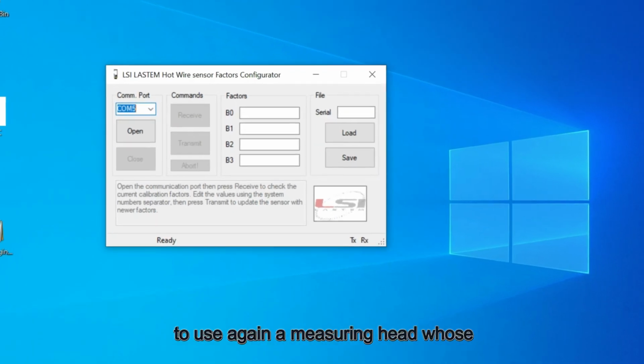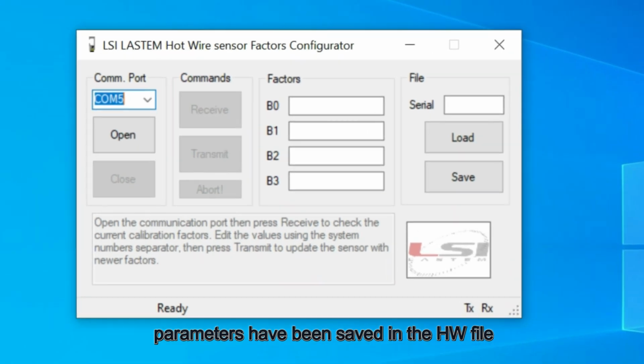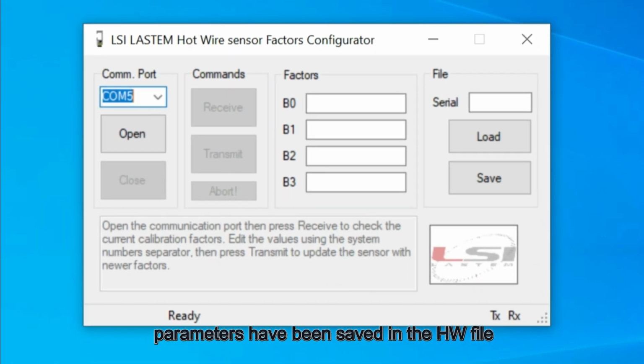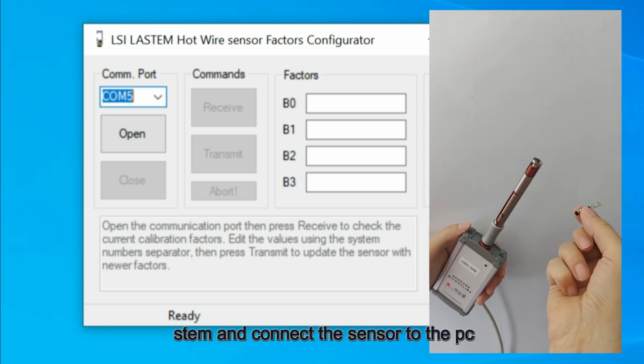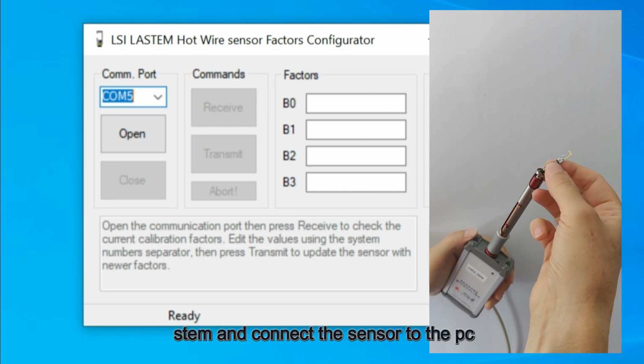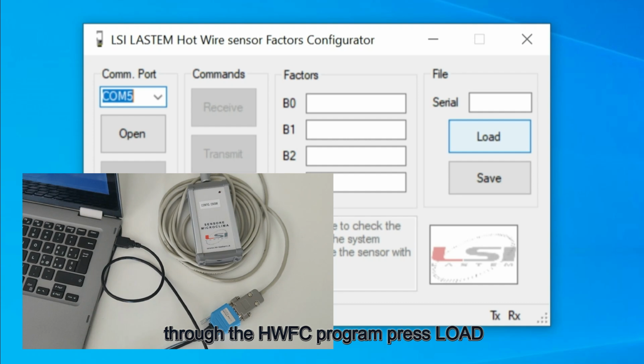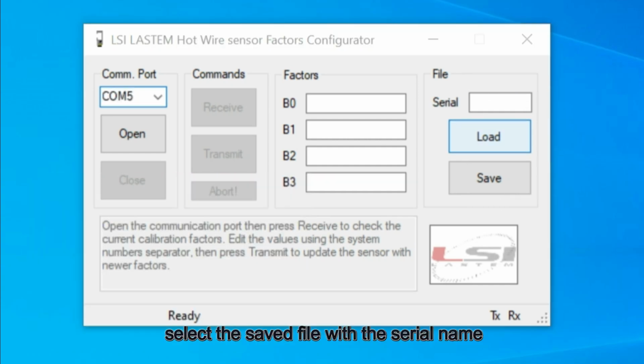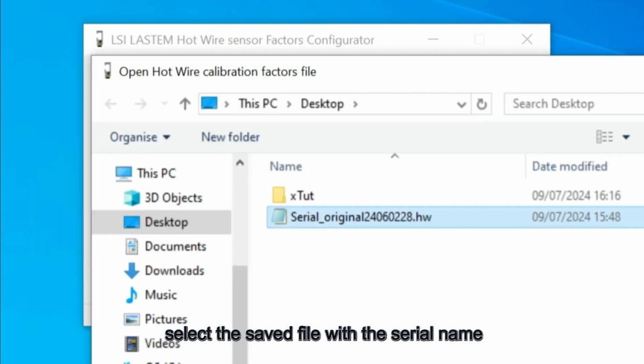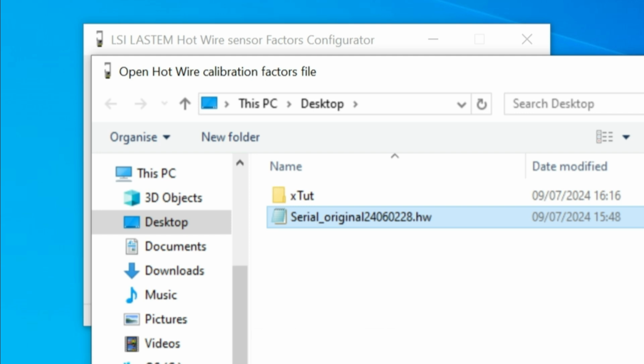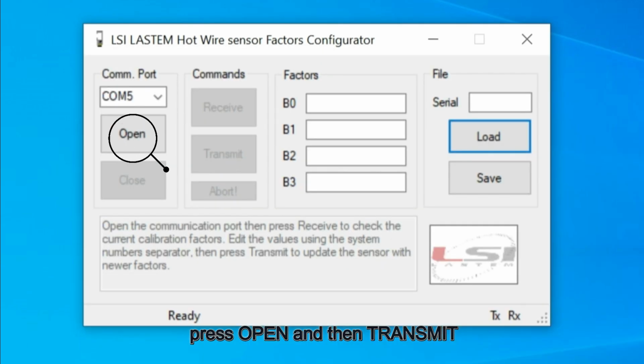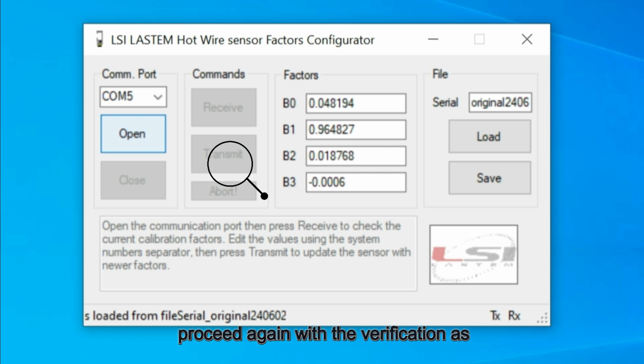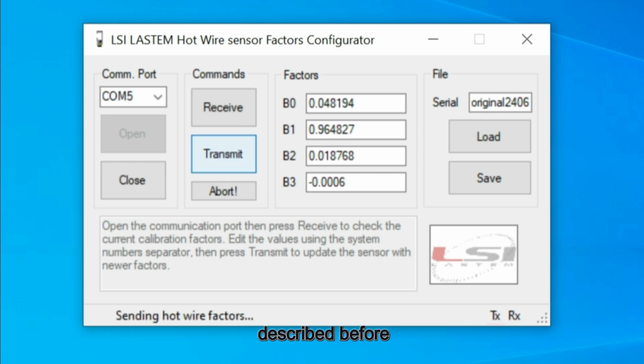To use again a measuring head whose parameters have been saved in the .hw file, the original one in this example, mount the original measuring head on the stem and connect the sensor to the PC. Through the HWFC program, press Load, select the saved file with the serial name of the head in use, press Open and then Transmit. Proceed again with the verification as described before.